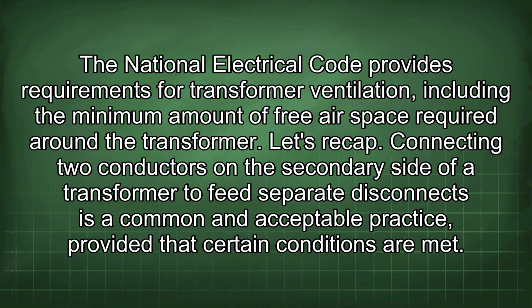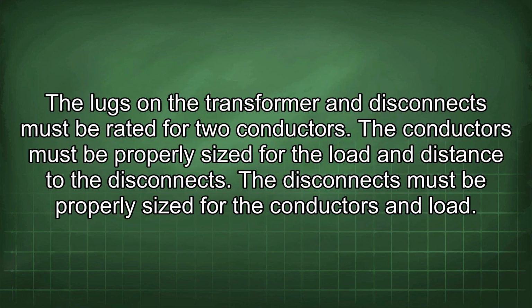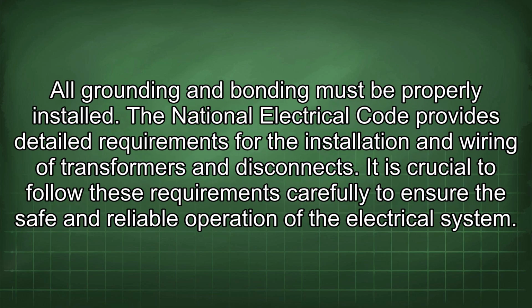Let's recap. Connecting two conductors on the secondary side of a transformer to feed separate disconnects is a common and acceptable practice, provided that certain conditions are met. The lugs on the transformer and disconnects must be rated for two conductors. The conductors must be properly sized for the load and distance to the disconnects. The disconnects must be properly sized for the conductors and load. All grounding and bonding must be properly installed. The National Electrical Code provides detailed requirements for the installation and wiring of transformers and disconnects. It is crucial to follow these requirements carefully to ensure the safe and reliable operation of the electrical system.